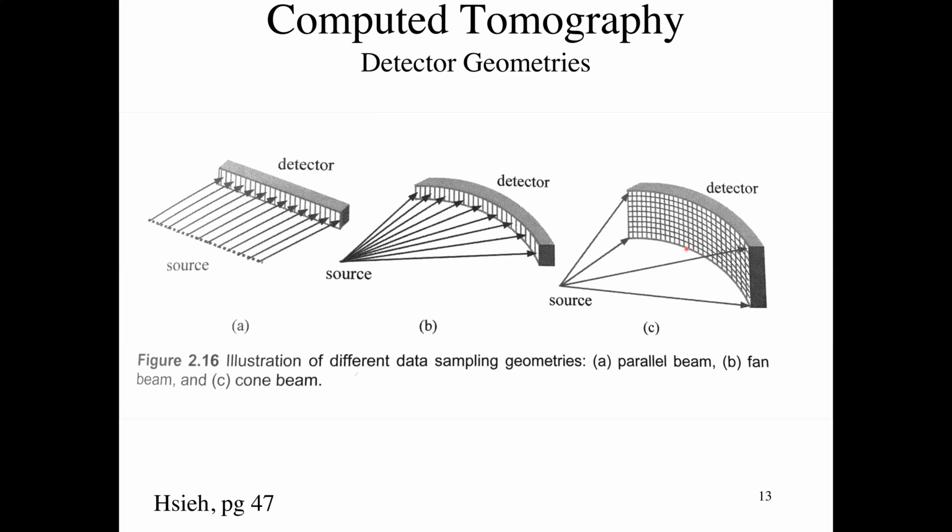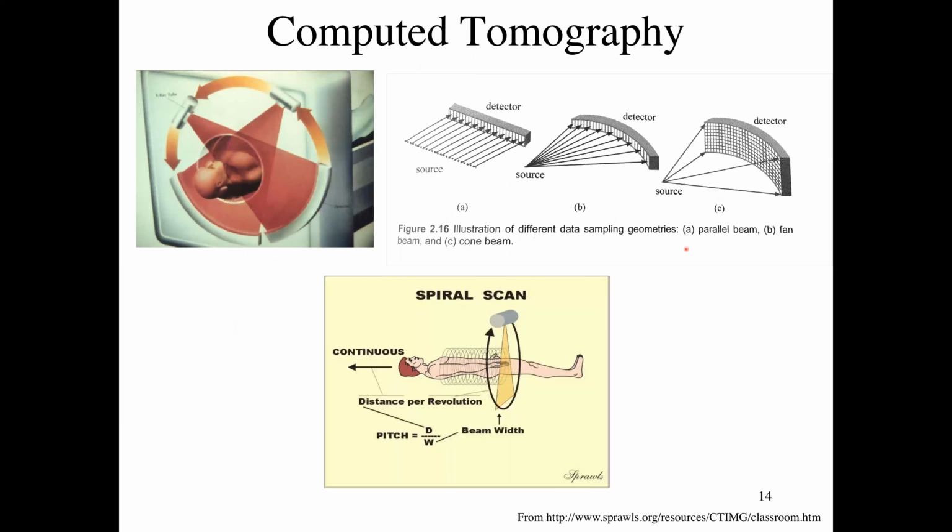So you can image a chunk, something about that big, a 16-centimeter sphere in the middle of the scanner. You can image it with 1/2 rotation of the gantry of a CT scanner. So that's about 140 milliseconds. You can image that entire volume. Huge leap in speed and technology.